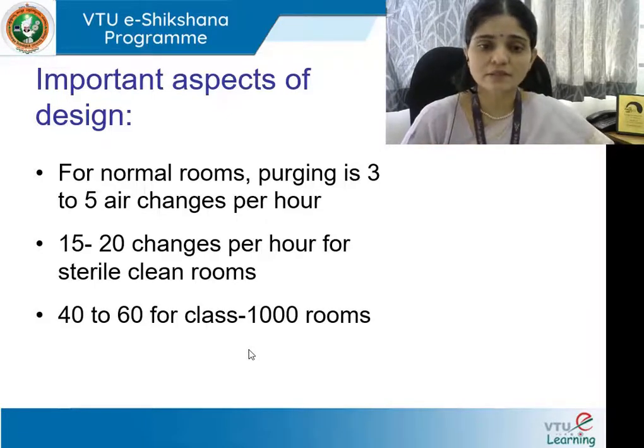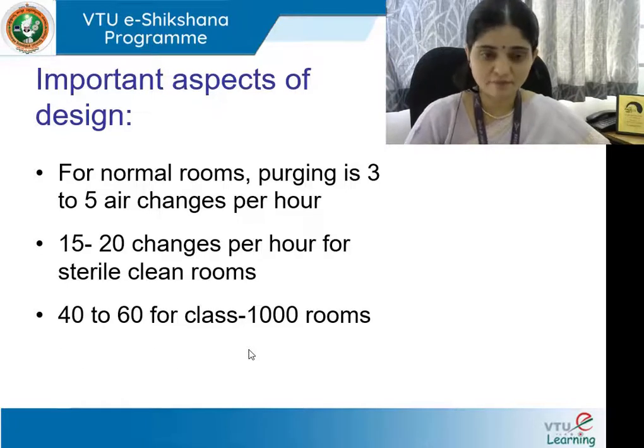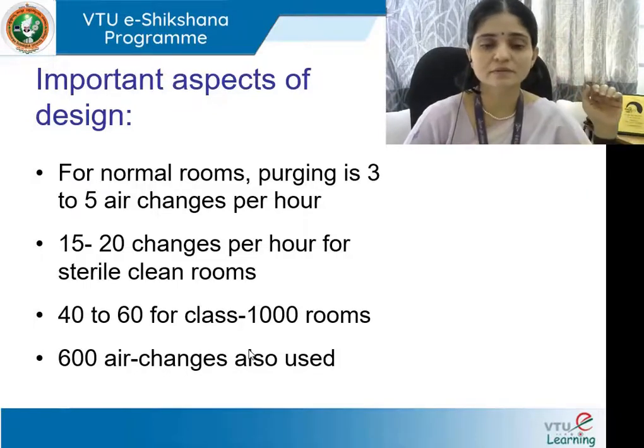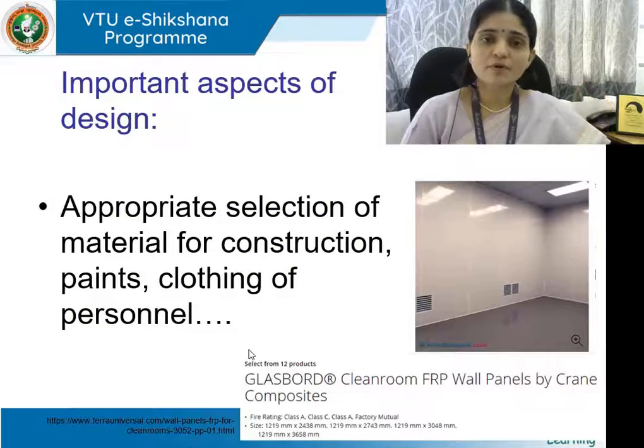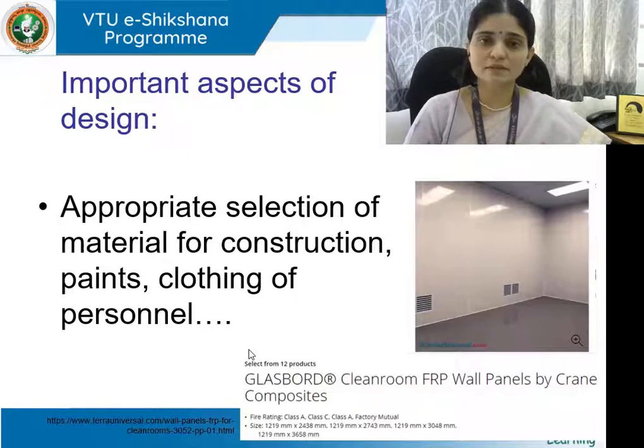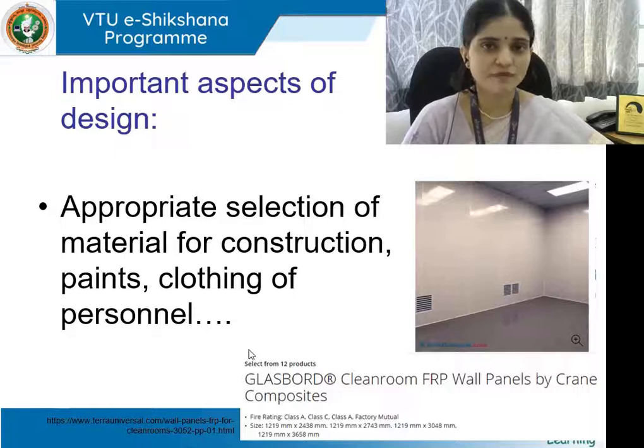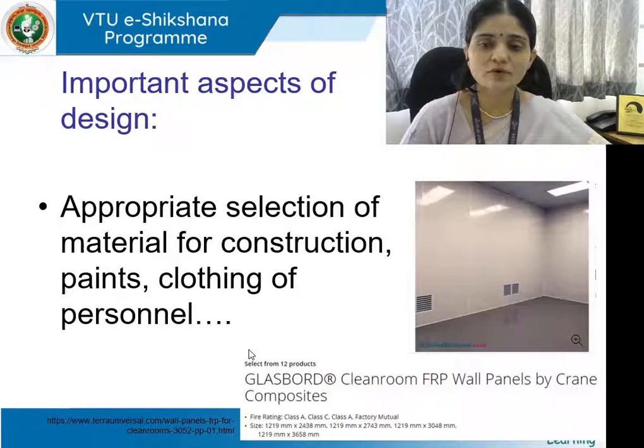For class 1000 rooms with very high cleanliness expectations, 40 to 60 air changes per hour are required. 600 air changes per hour are used in certain critically required clean rooms. Appropriate selection of materials for construction, paints, and clothing for personnel must all be methodologically in place. FRP wall panels, for example, are very smooth and unlikely to release residue or dust into the space — smooth surfaces are preferred over coarse ones.